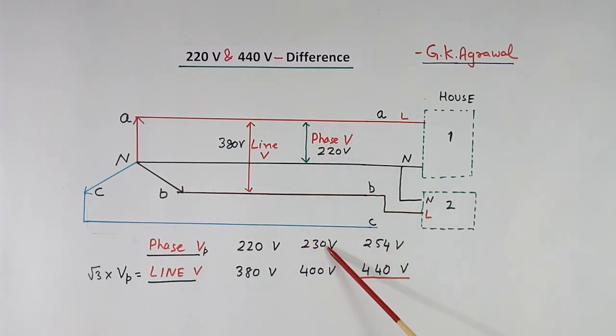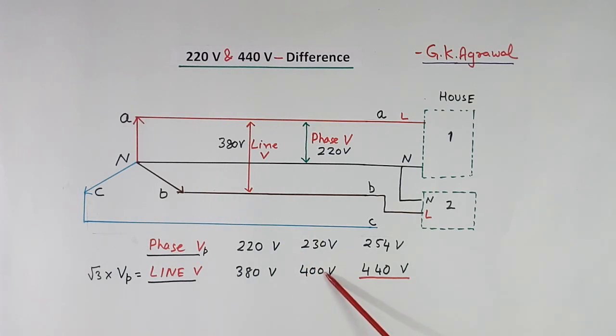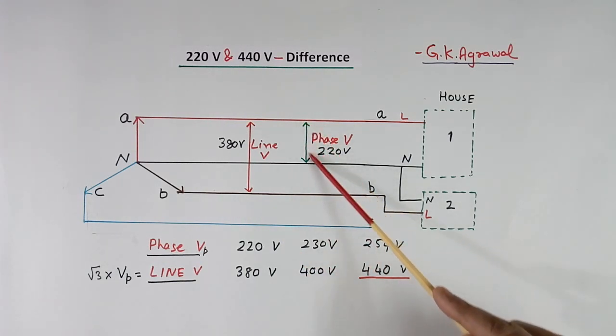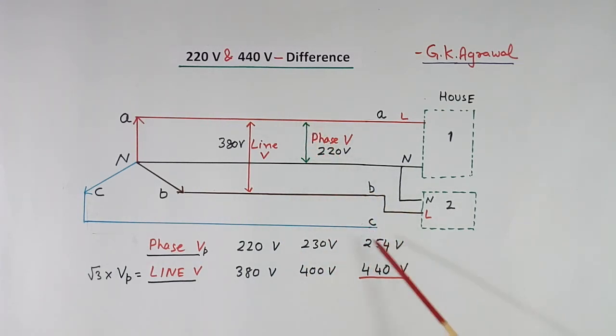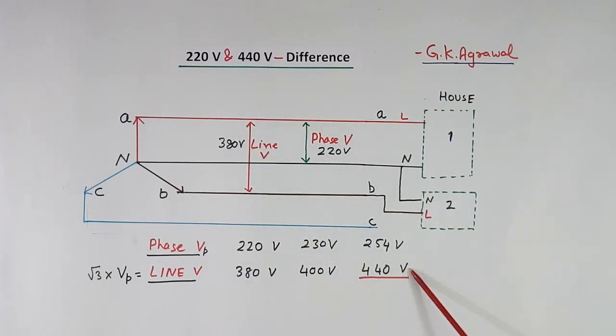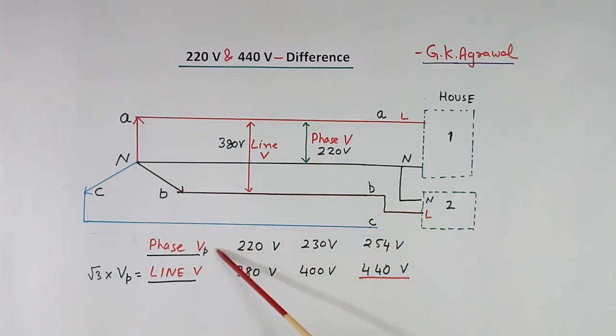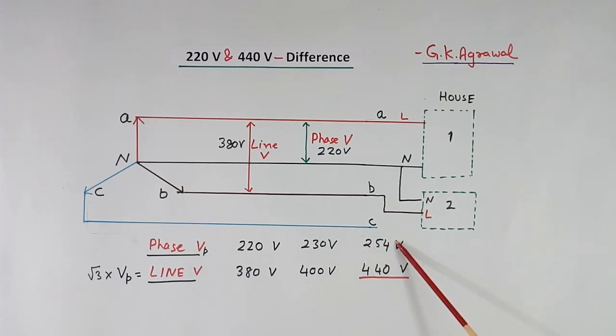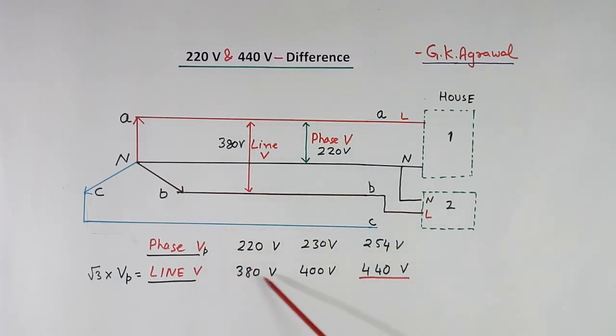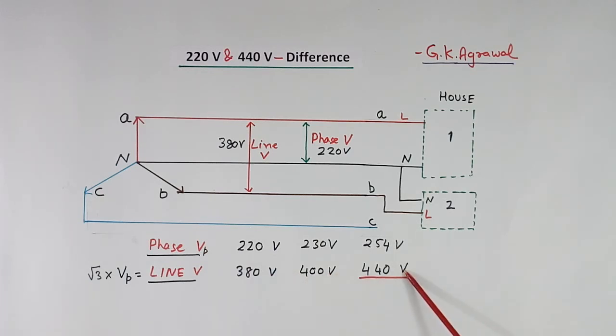If this phase voltage is 230V, line to line you will get 400V. Similarly, if this phase voltage is 254V, the line-to-line voltage is 440V. This phase voltage will change — it may be less than 220V, may be 220V, may be 230V, may be 254V. So line-to-line voltage may be less than 380V, 380V, 400V, or 440V.